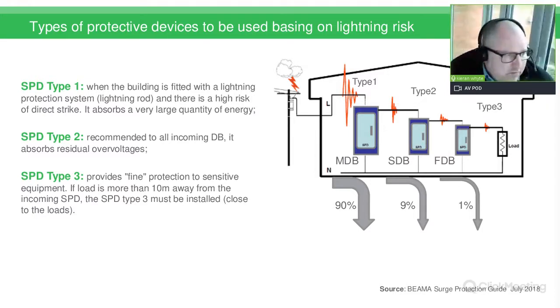If the load is more than 10 meters away from the incoming surge protection device, then an SPD type 3 must be installed. These are the type that you commonly see in extension leads, offering protection to the devices that are plugged into those leads.